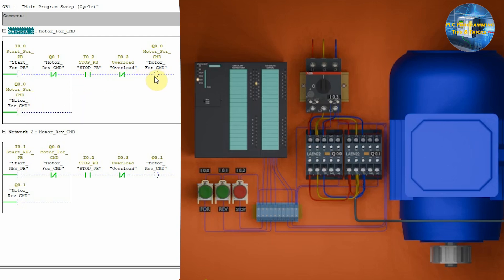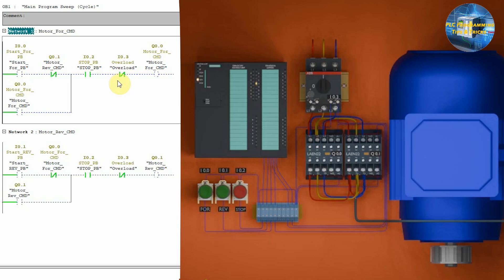Next, we have a normally open contact I0.2 of the stop push button and a normally closed contact of overload I0.3 in series with the motor forward command Q0.0.